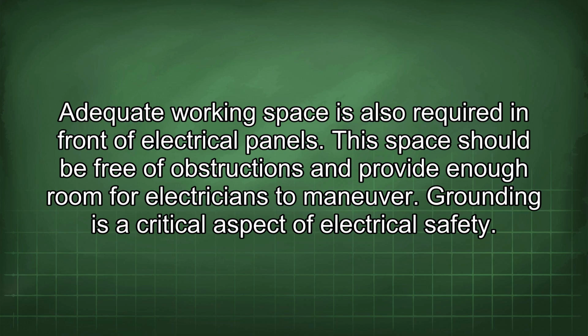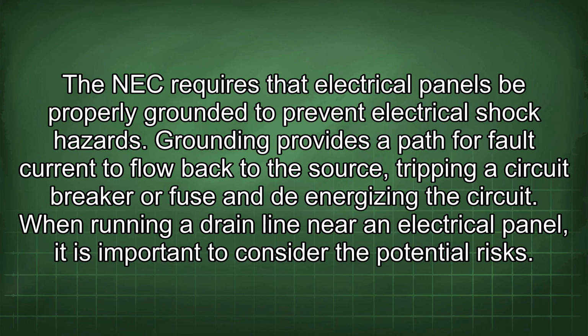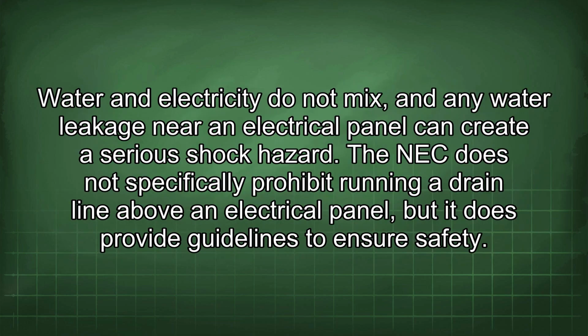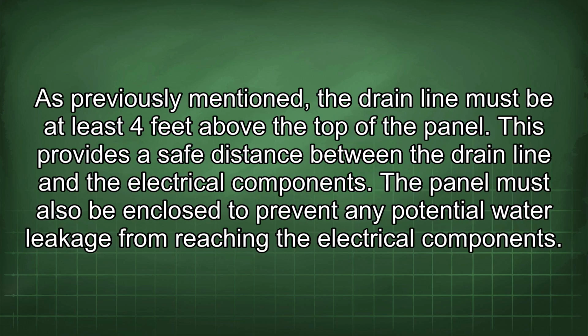Grounding is a critical aspect of electrical safety. The NEC requires that electrical panels be properly grounded to prevent electrical shock hazards. Grounding provides a path for fault current to flow back to the source, tripping a circuit breaker or fuse and de-energizing the circuit. When running a drain line near an electrical panel, it is important to consider the potential risks. Water and electricity do not mix, and any water leakage near an electrical panel can create a serious shock hazard. The NEC does not specifically prohibit running a drain line above an electrical panel, but it does provide guidelines to ensure safety. As previously mentioned, the drain line must be at least 4 feet above the top of the panel.